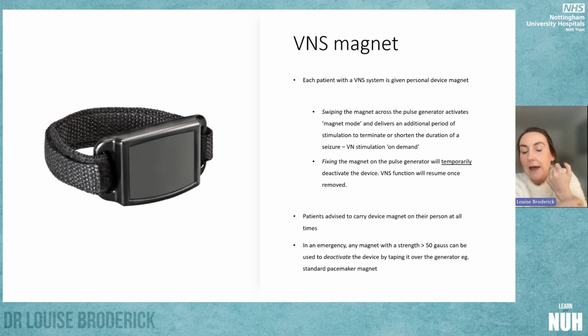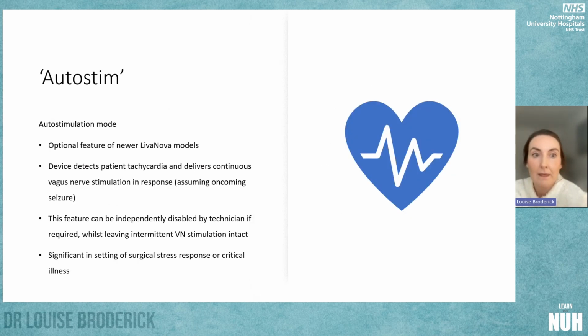However, in an emergency, if the patient doesn't have their device magnet and the device needs to be urgently deactivated, for example in the setting of a critical bradyarrhythmia, any magnet with a strength over 50 Gauss can be used to deactivate the device by taping it onto the generator. A standard pacemaker magnet has a strength of 90 Gauss, so this can be used, and all theatre departments should have a pacemaker magnet easily accessible.